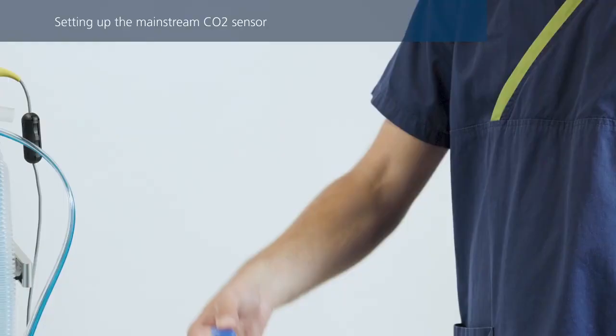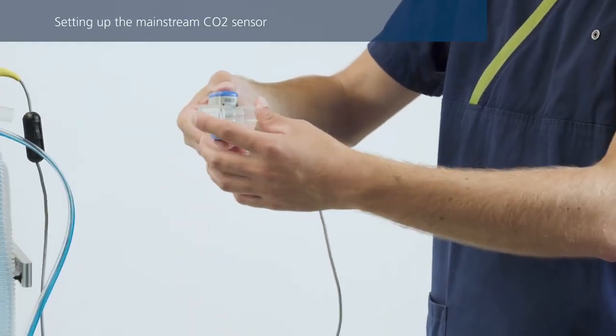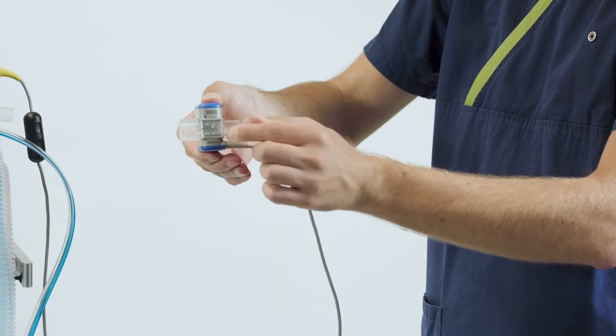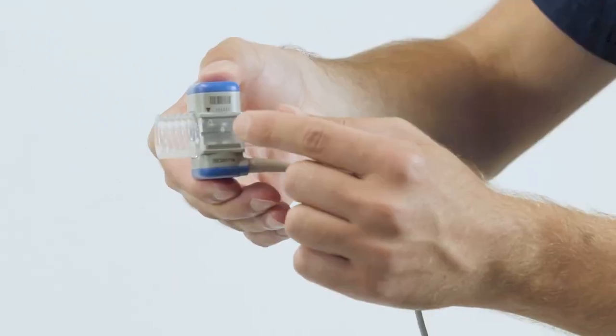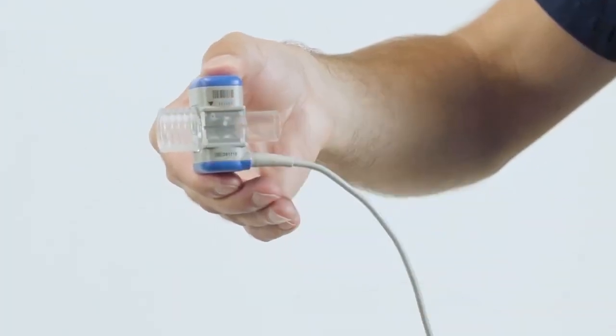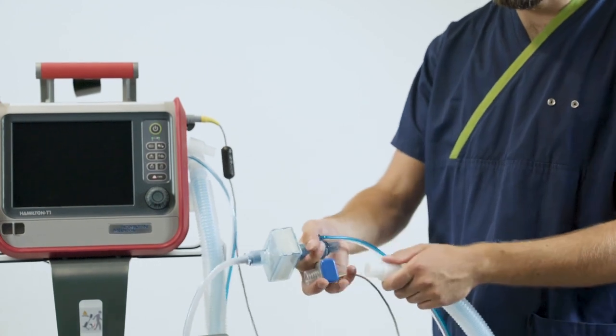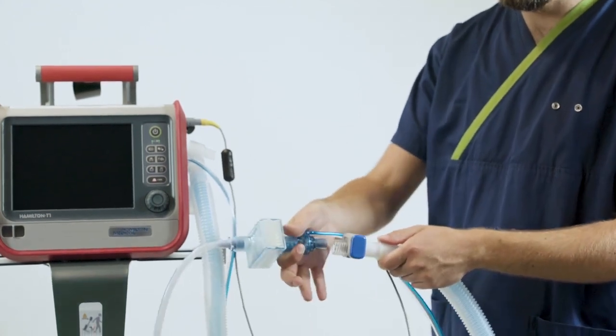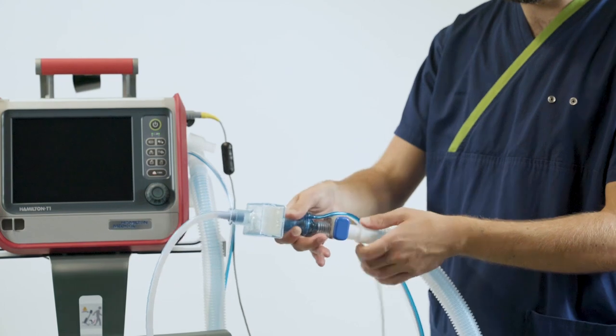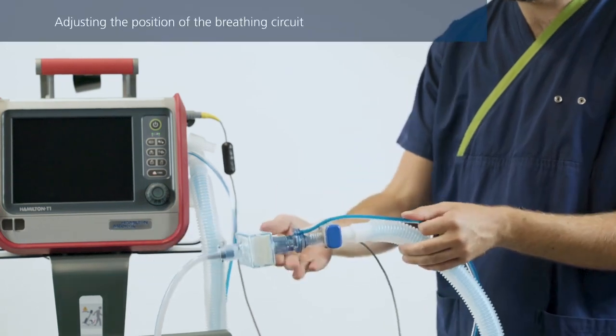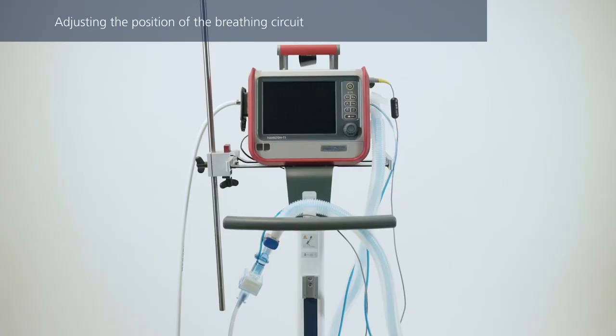If you are using a mainstream CO2 sensor, you can connect it now to the corresponding connection port. Slide the CO2 sensor onto the airway adapter, align the arrows on both components, and press them together until you hear a click. Then, connect the sensor with the airway adapter to the breathing circuit before the flow sensor. Position the breathing circuit so that the tubes cannot be pushed, pulled, or kinked if the patient moves.